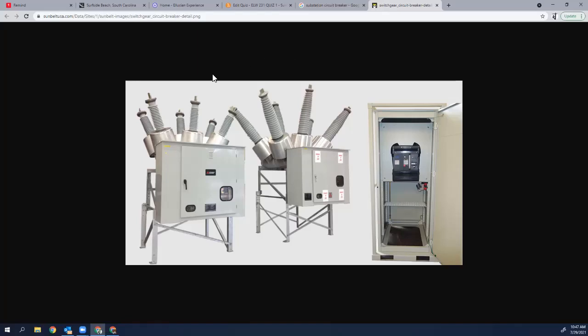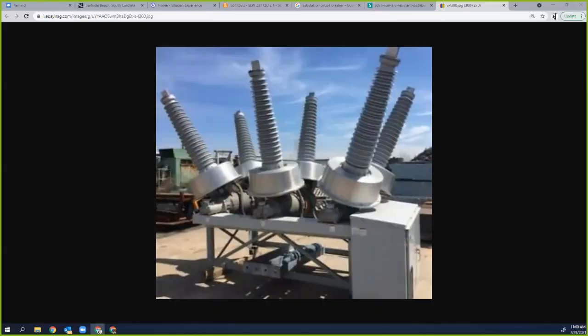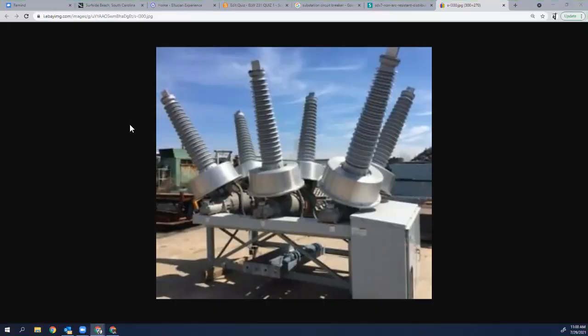Circuit breakers or transformer? Circuit breakers — perfect. So I showed you the relays inside the breaker itself, and at the bottom encased here are the CTs — current transformers. We're taking a very high current and transforming it so we can go into the control panel and meter and measure it. You can see the cabling coming off of the CTs getting that information over to the relay panel. The relay gets its information from the CT.